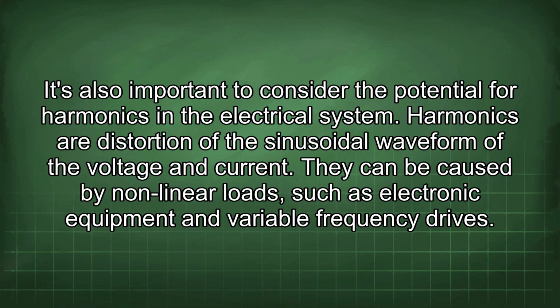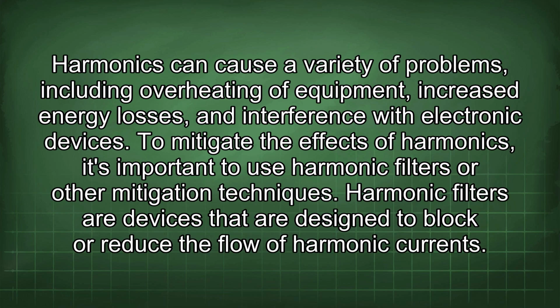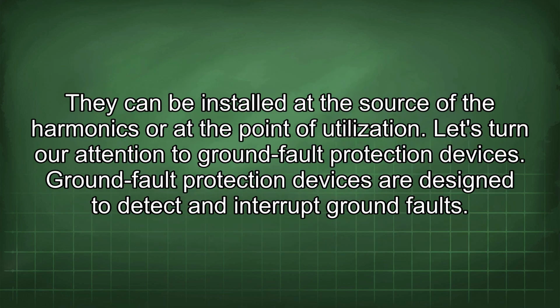It's also important to consider the potential for harmonics in the electrical system. Harmonics are distortion of the sinusoidal waveform of the voltage and current. They can be caused by nonlinear loads such as electronic equipment and variable frequency drives. Harmonics can cause a variety of problems, including overheating of equipment, increased energy losses, and interference with electronic devices. To mitigate the effects of harmonics, it's important to use harmonic filters or other mitigation techniques. Harmonic filters are devices that are designed to block or reduce the flow of harmonic currents. They can be installed at the source of the harmonics or at the point of utilization.